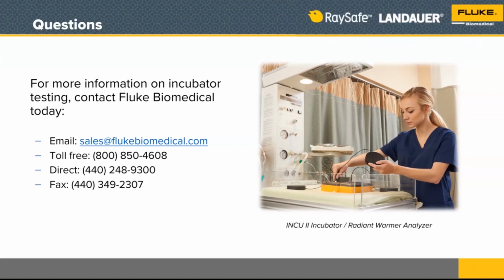Another question was, how often should I check my incubator? The majority of manufacturers agree once per year. We have a little different point of view here at Fluke Biomedical. We think twice per year might be better because of how important it is to the neonates that are going to be in the incubator. So how often do the test instruments need to be calibrated? That's a great question too, a really great question.